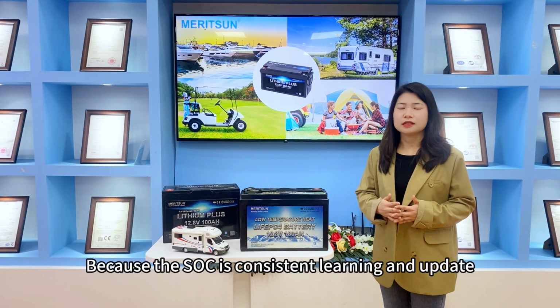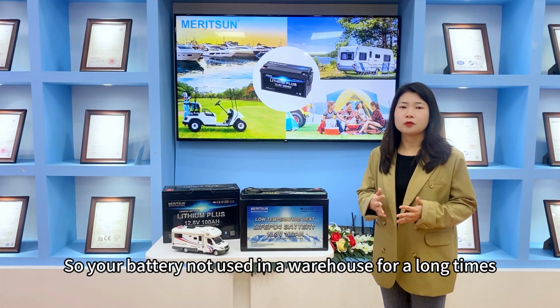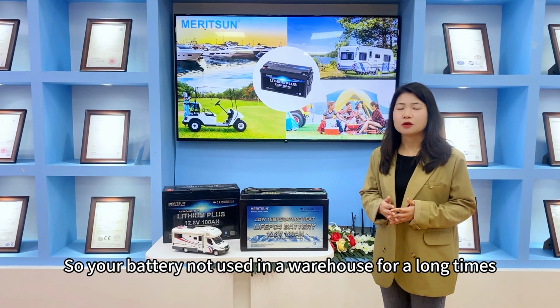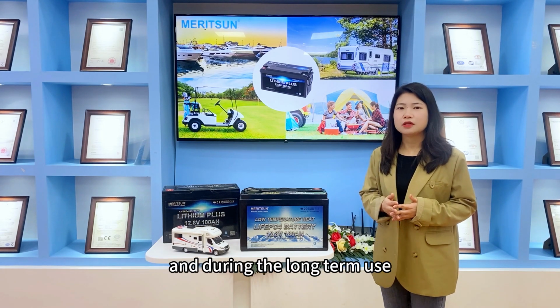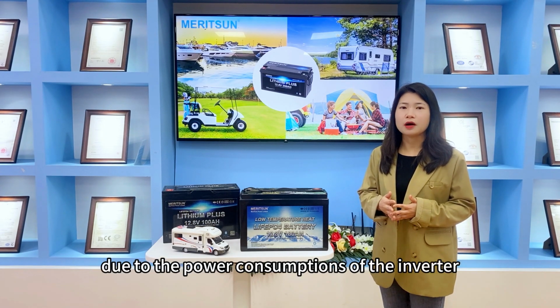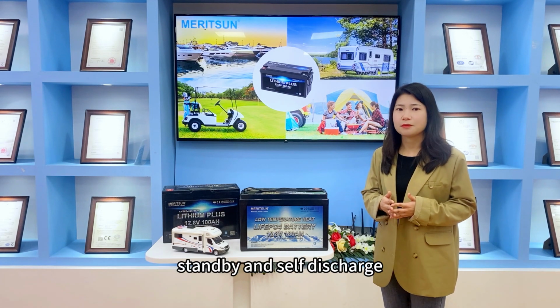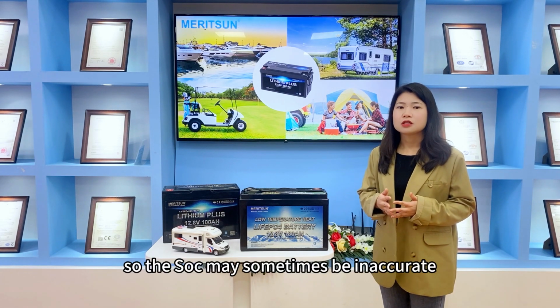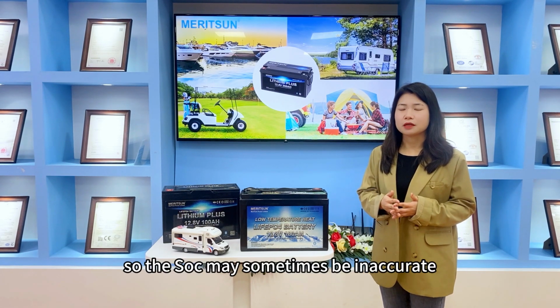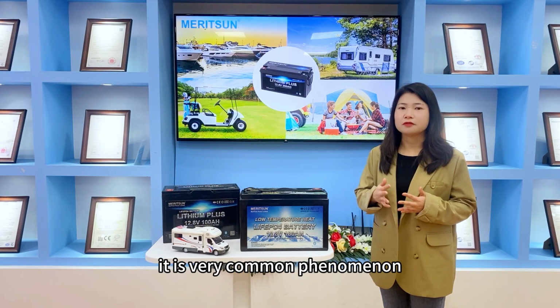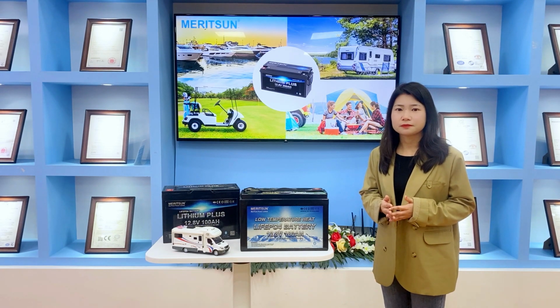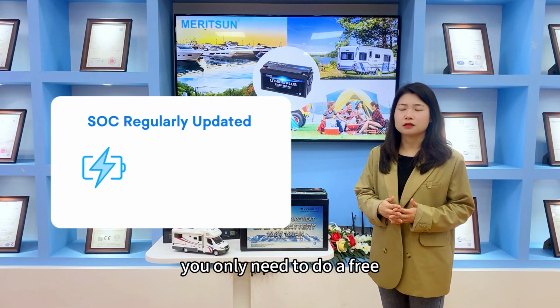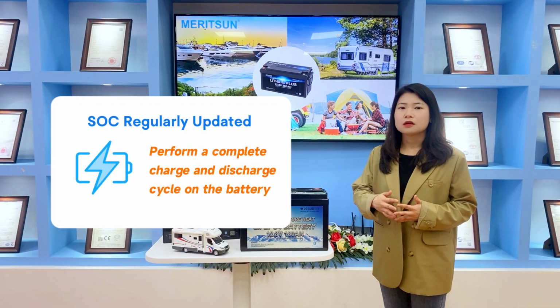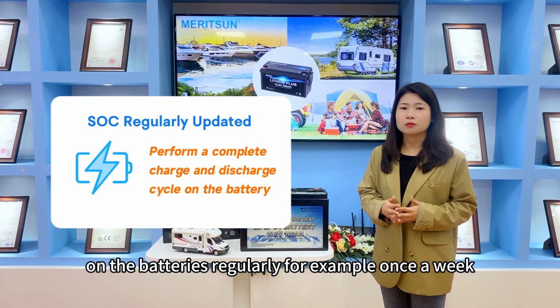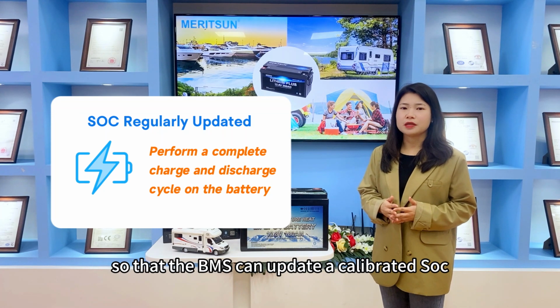Because the SOC is constantly learning and updating, if your battery is not used for a long time, or during long-term use, due to power consumption from inverter standby and self-discharge, the SOC may sometimes become inaccurate. This is a very common phenomenon. You only need to do a full charge and discharge cycle on the battery regularly, for example once a week, so that the BMS can update and calibrate the SOC.